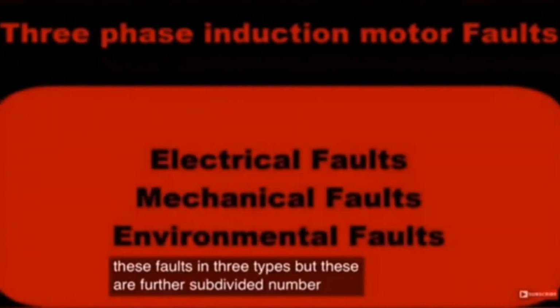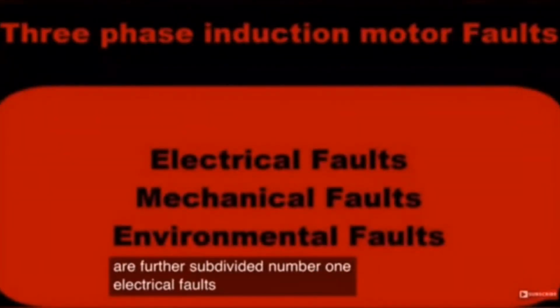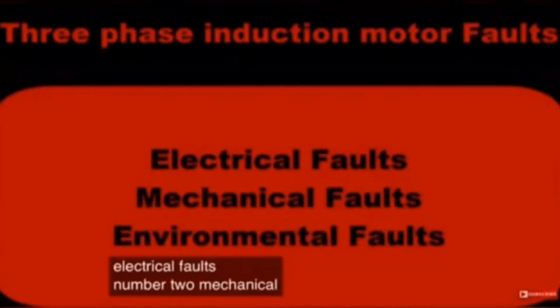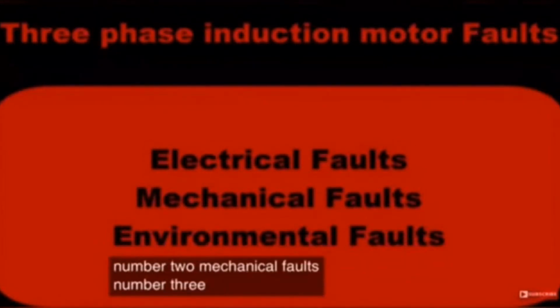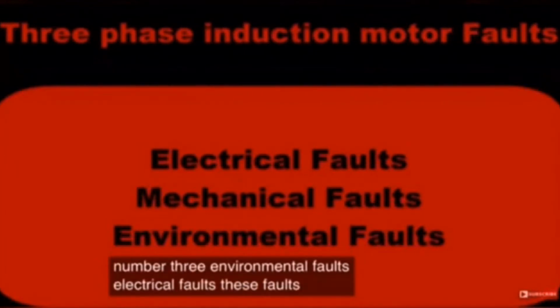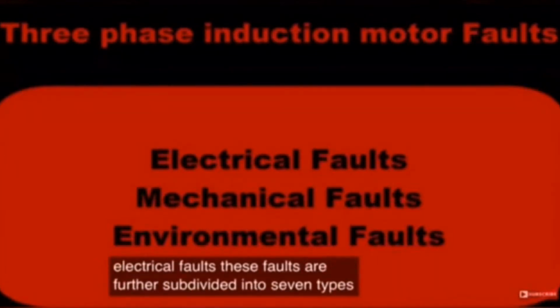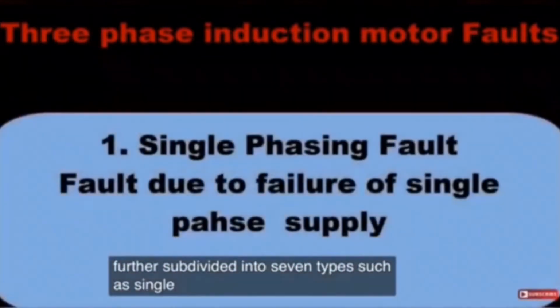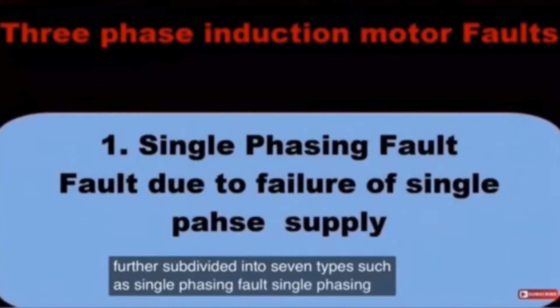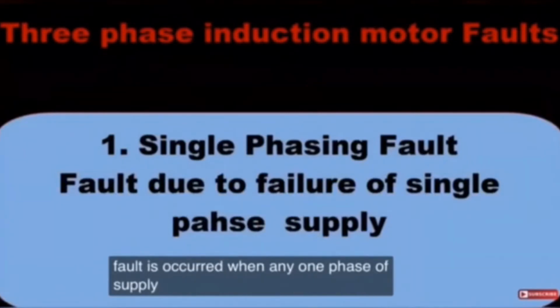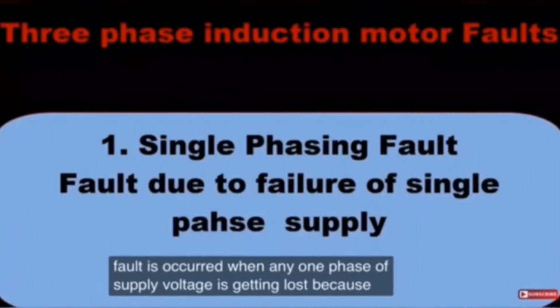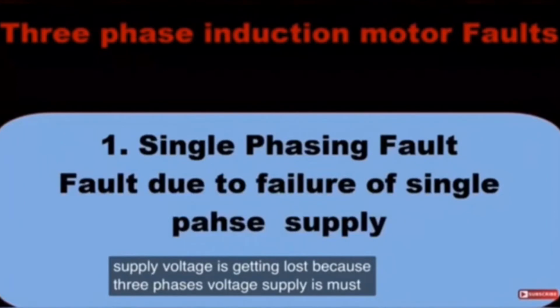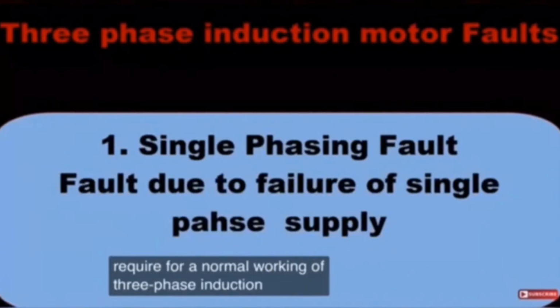Subdivided. Number 1, electrical faults. Number 2, mechanical faults. Number 3, environmental faults. Electrical faults. These faults are further subdivided into 7 types such as single phasing fault. Single phasing fault occurs when any one phase of supply voltage is lost, because 3 phases voltage supply is required for normal working of a 3-phase induction motor. Due to this fault the motor could be burned or heat up.